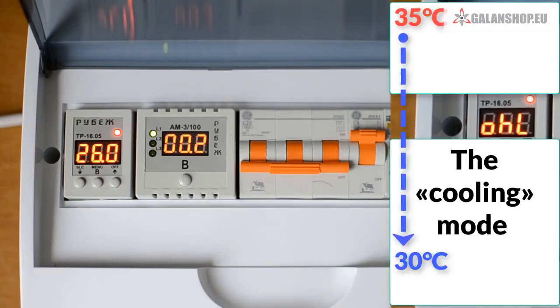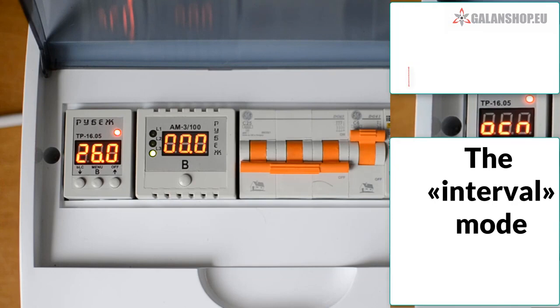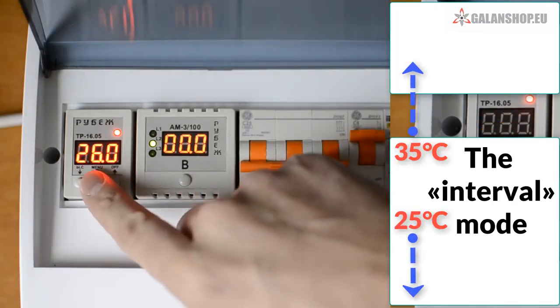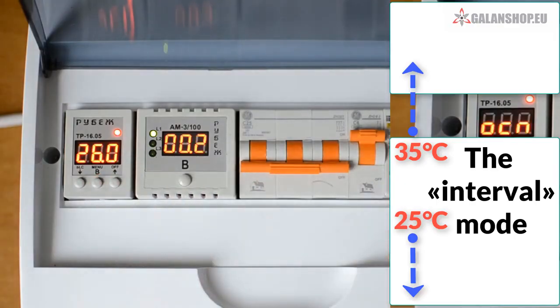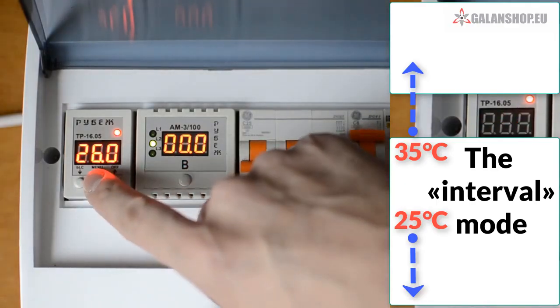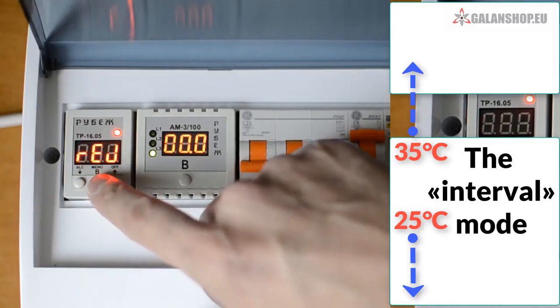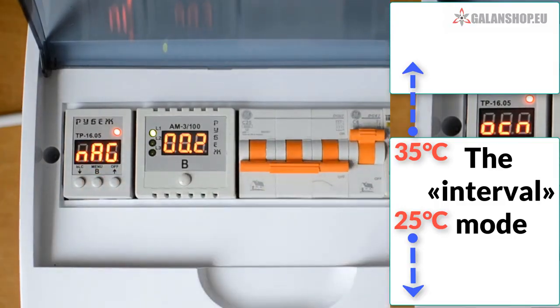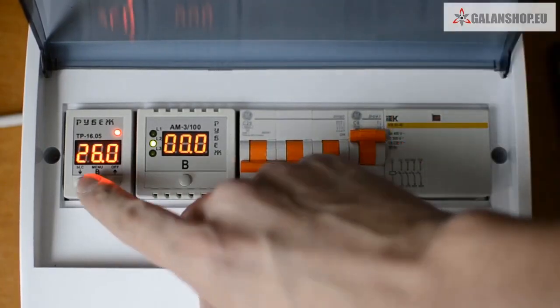When the cooling mode is selected, if the requested temperatures are 30 and 35 degrees, the controller will turn on, say, a cooling unit at the temperature of 35 degrees and will turn it off at the temperature of 30 degrees. In this way, your cooling unit is going to work in the range of 30 to 35 degrees. The third mode, interval mode: if the requested temperature is set to 30 degrees and the hysteresis is set to 5 degrees, the controller will make it turn on in the range of 25 to 35 degrees and will make it turn off if the temperature is above 35 degrees or below 25 degrees.